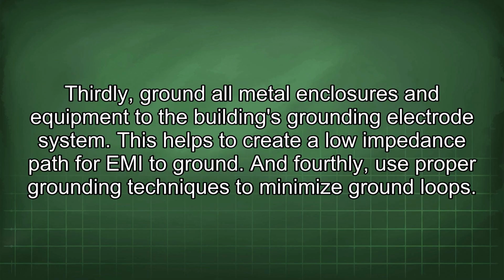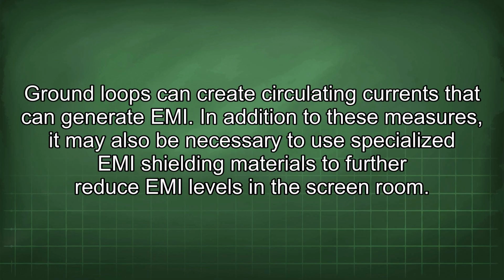Thirdly, ground all metal enclosures and equipment to the building's grounding electrode system. This helps to create a low impedance path for EMI to ground. And fourthly, use proper grounding techniques to minimize ground loops. Ground loops can create circulating currents that can generate EMI. In addition to these measures, it may also be necessary to use specialized EMI shielding materials to further reduce EMI levels in the screen room.